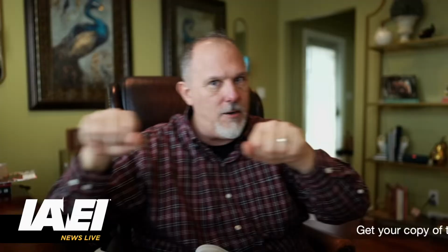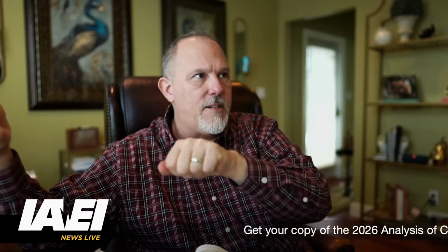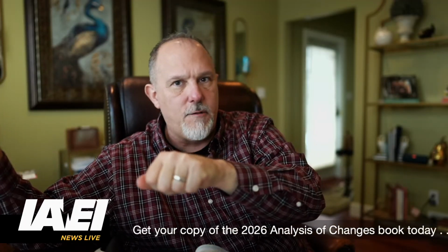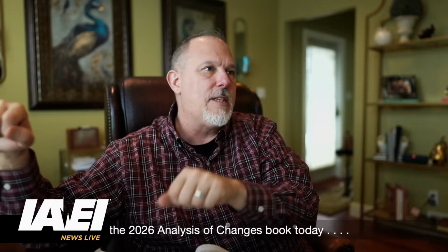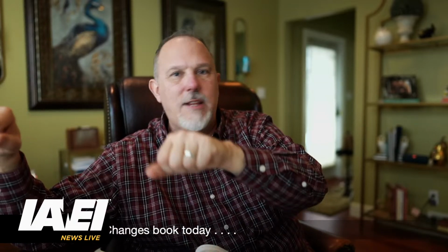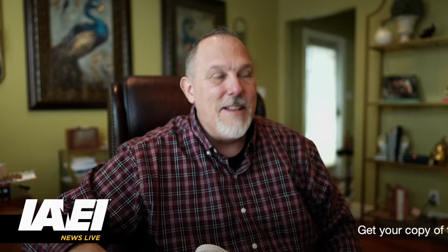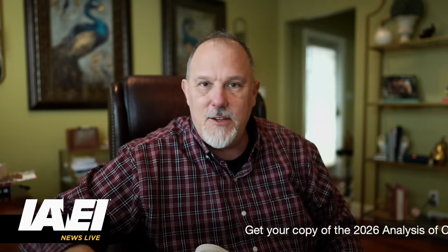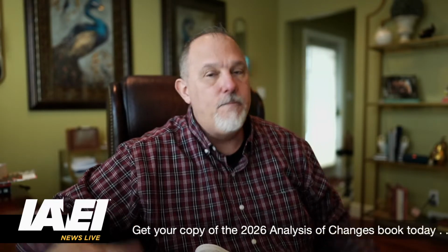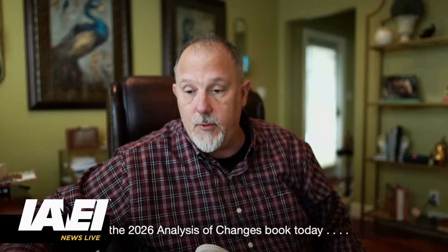So there's two schools of thought, and the battle going on is like a tug of war. It goes this way—oh yeah, we're going to remove all the GFCI requirements out of 210.8 and put it in 422—then someone says, hold on, we're just using that to identify which branch circuit, and it goes back the other way. God only knows where it's going next cycle, but the battle and the struggle is real, and it's not going away.